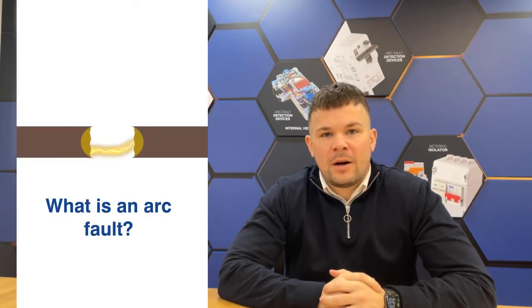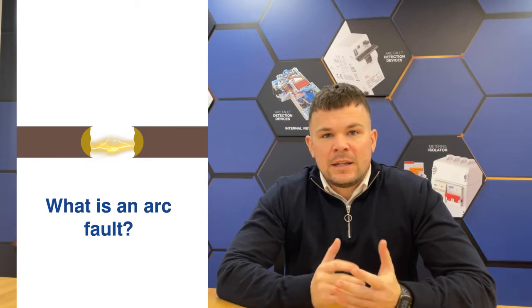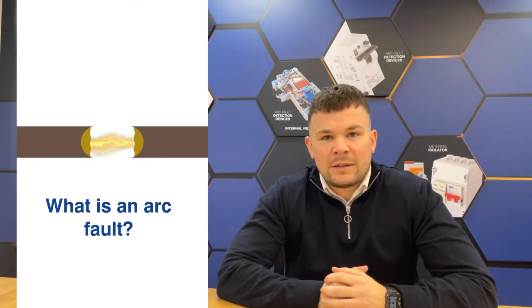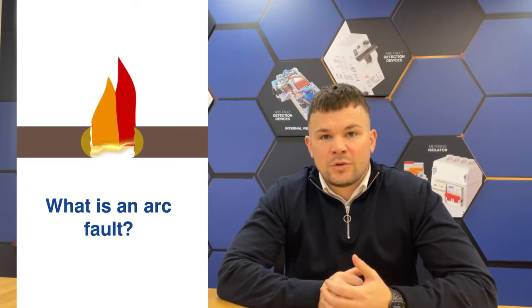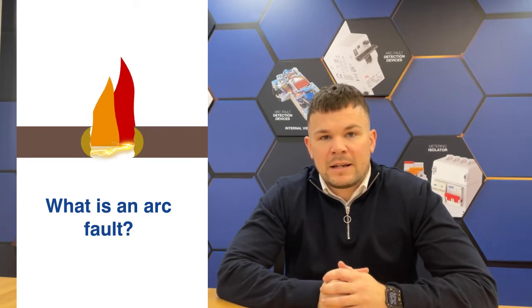So, what is an arc fault? An arc fault occurs when loose or corroded connections make intermittent contact and cause sparking or arcing between these connections. This translates into heat, which will break down the insulation of the wire and potentially trigger an electrical fire. Such arcs can range in power and vary a great deal in strength and duration.